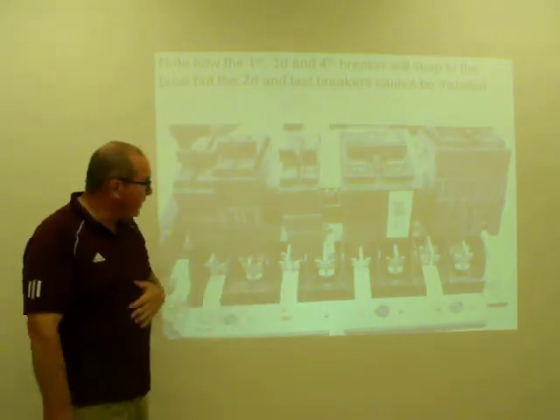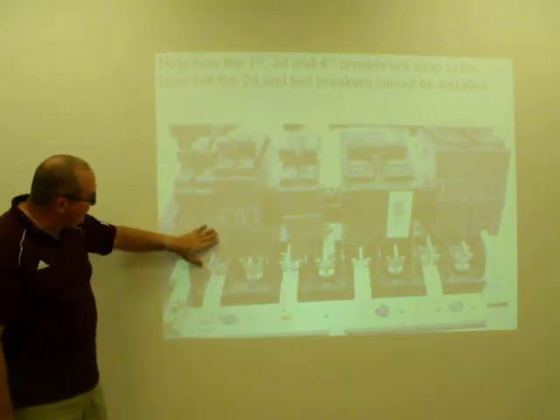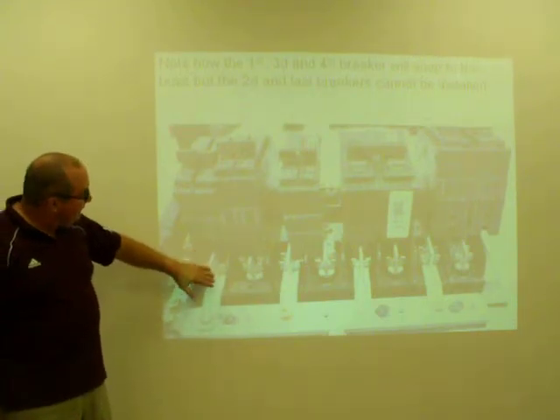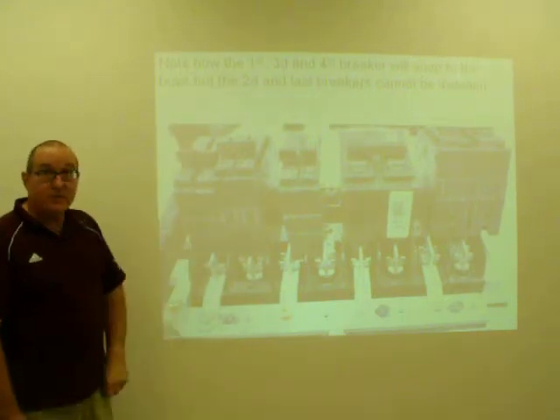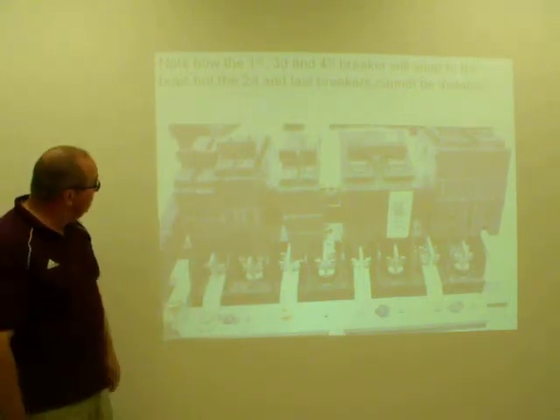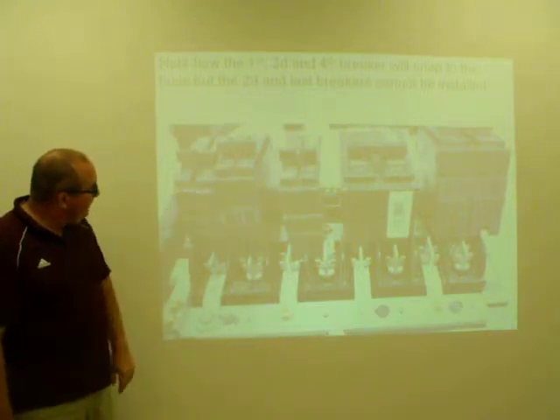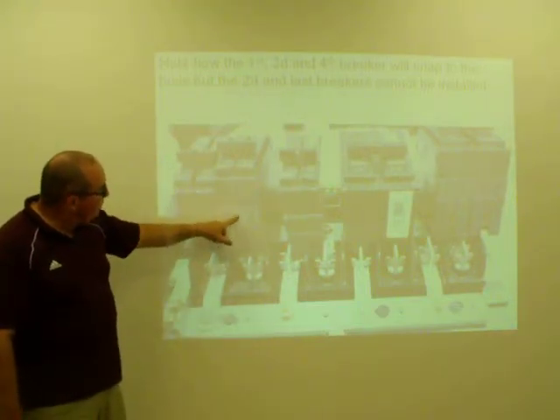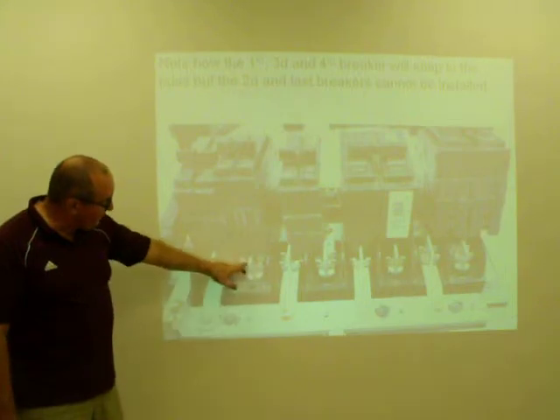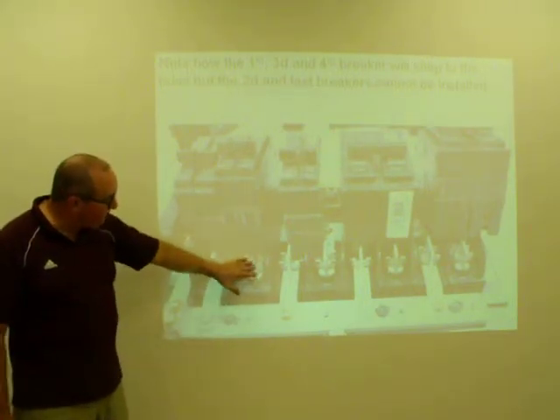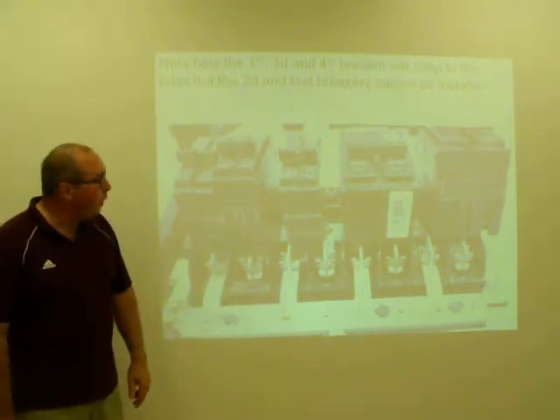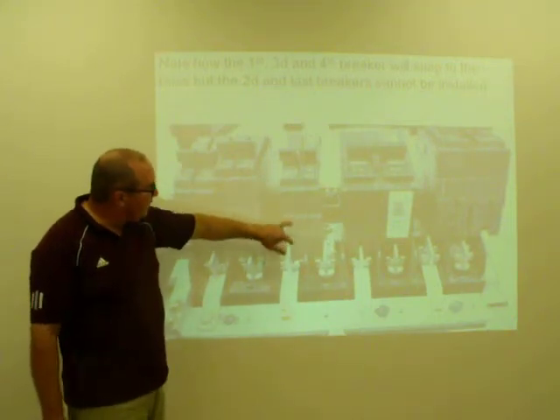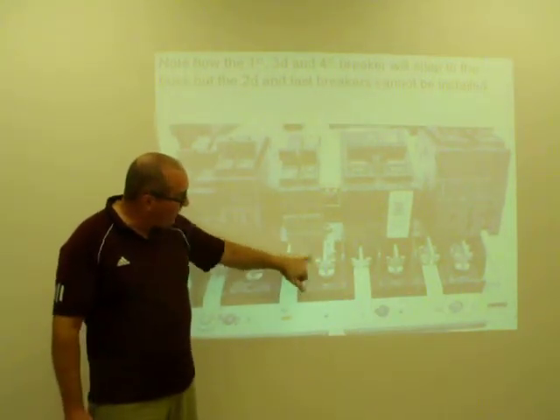This gives you a little better idea of what we're talking about. You can see here this breaker fully seated. That's a GE breaker. It should fully seat in a GE panel. That's 2 singles. This is a GE 2-pole breaker, and obviously, as I showed you, it will not fit when you're trying to get it on the same pole. Here's a similar GE breaker that will fit when it is on 2 poles.